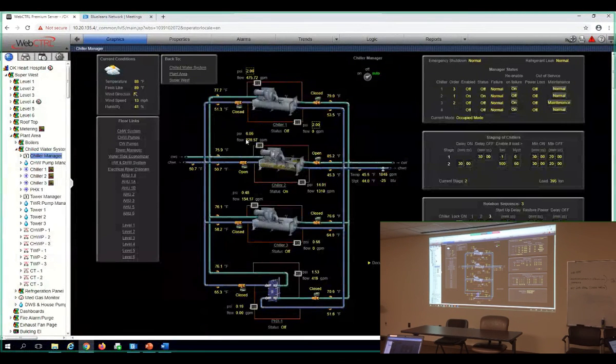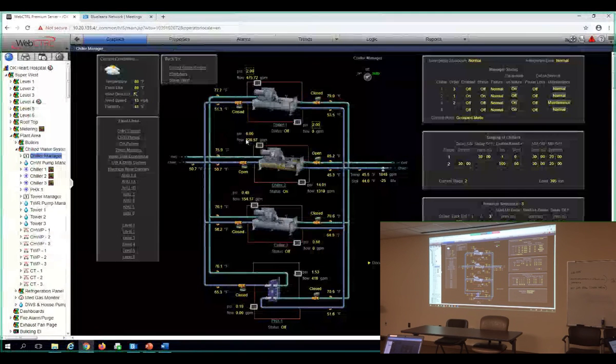What I originally tried to do when I opened my second chiller was just start another pump and run water through it, because I didn't need another tower on. But I blew the pipe apart on the spray water. So now I actually start another tower pump, run that water till I'm ready to shut down that other chiller. So that may be the only odd thing to see when you go through rotations. That chiller rotates, you're actually going to see the tower down. Yeah, that's kind of cool.